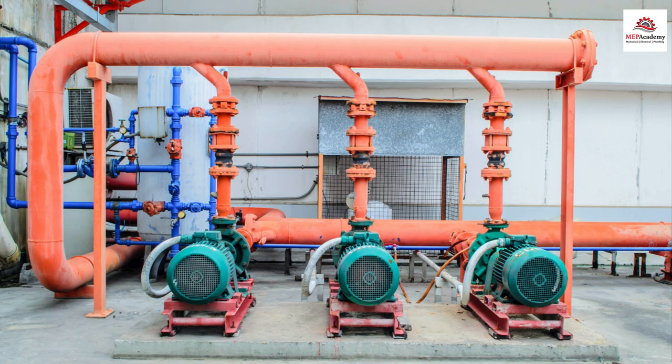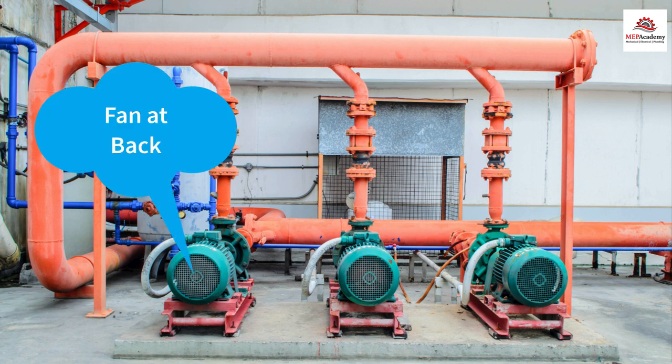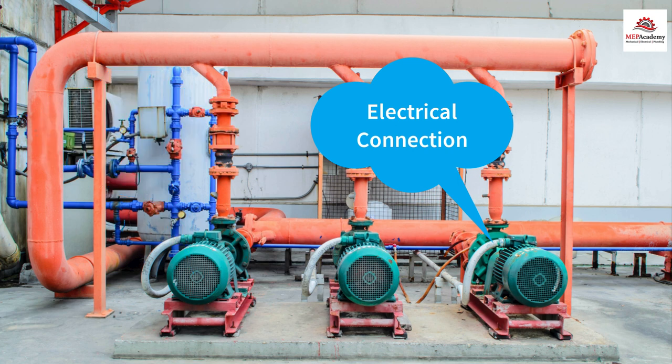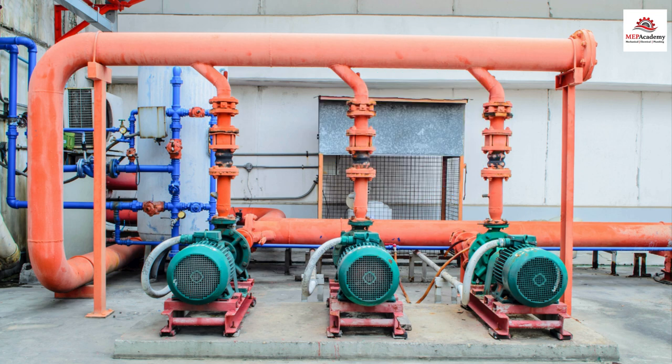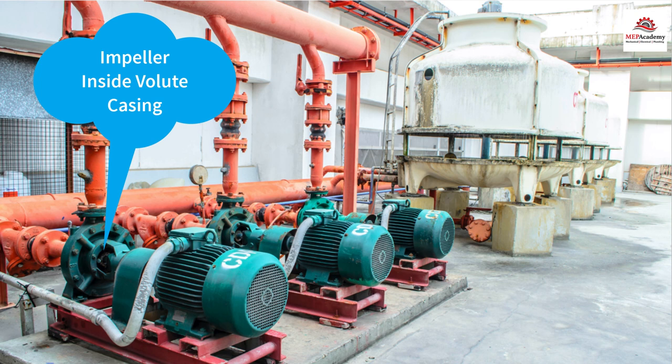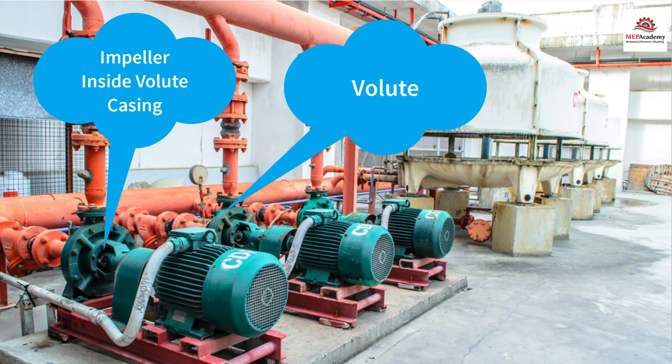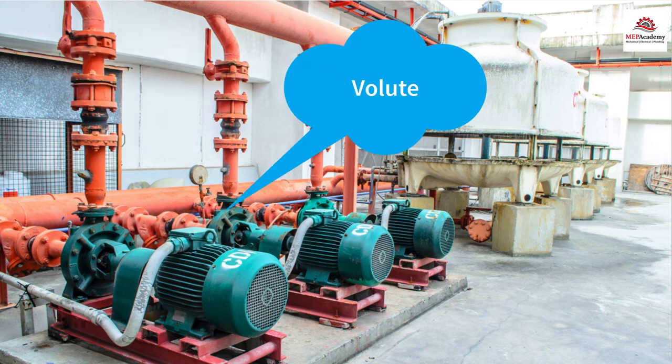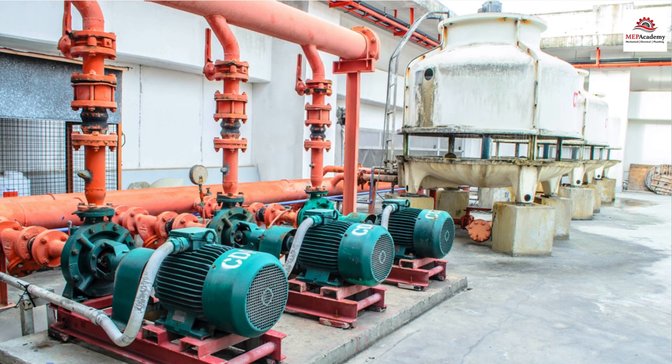Disassembling the pump, we see that the motor has a fan to keep it cool when running. The motor converts electrical energy into mechanical energy and spins the shaft. See our video on how motors work. Attached to the shaft is an impeller which is housed inside a volute, the protective casing surrounding the impeller, and which acts as a guide for the water being forced out of the impeller by the spinning centrifugal force.